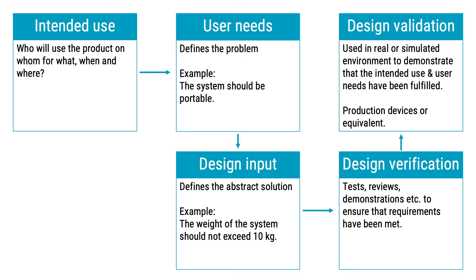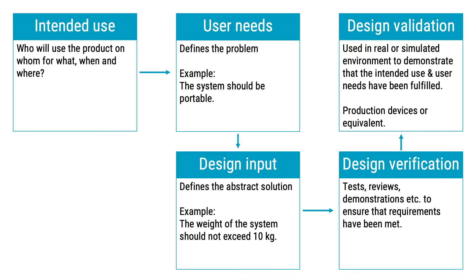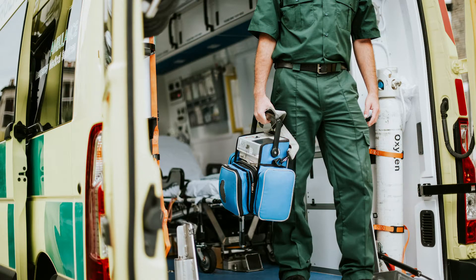To avoid that, you should perform design validation. It is a regulatory requirement to perform design validation, and it must be done by testing your device design in a real or simulated environment using production units or equivalent devices. For our portable product example, we might let a few users carry the device and conclude that yes, the device is portable. However, it is not always that easy — sometimes you cannot show that intended use and user needs have been met with anything less than a clinical investigation on real human subjects.